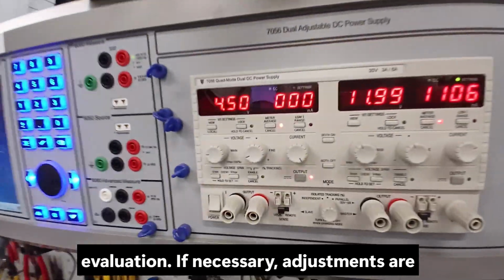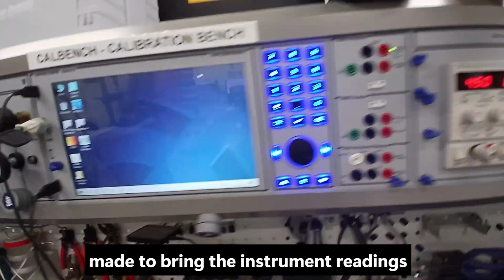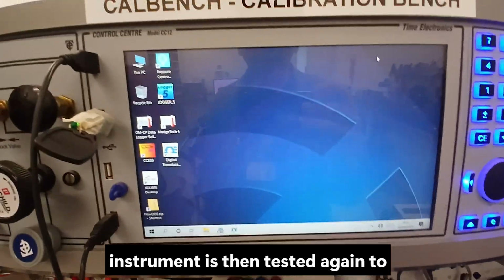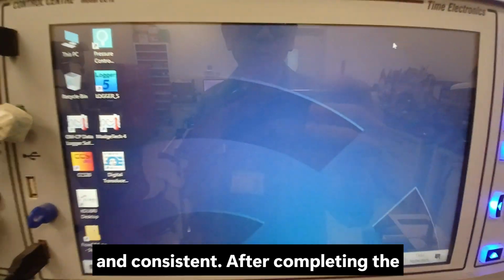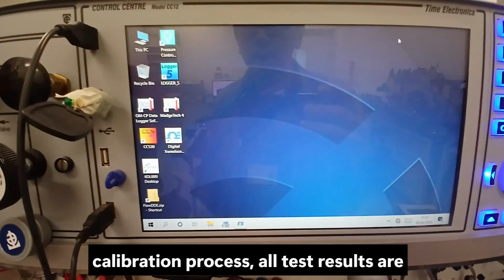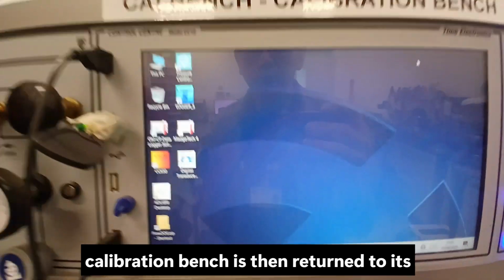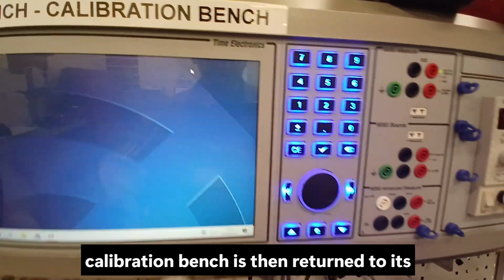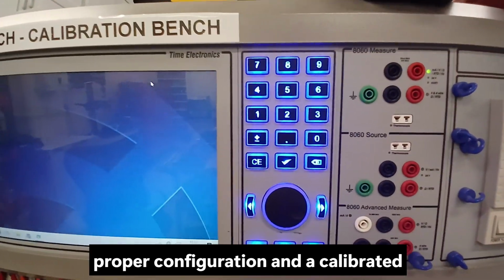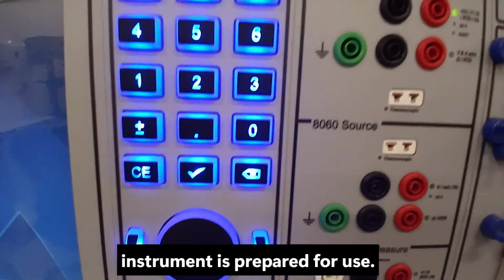If necessary, adjustments are made to bring the instrument readings within the required accuracy limits. The instrument is then tested again to confirm that the calibration is correct and consistent. After completing the calibration process, all test results are documented for future reference. The calibration bench is then returned to its proper configuration, and the calibrated instrument is prepared for use.